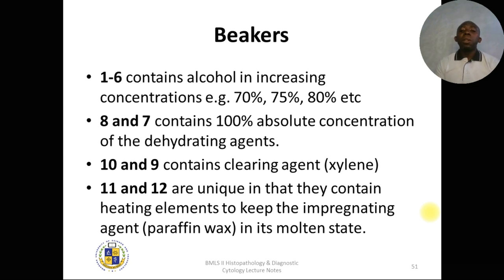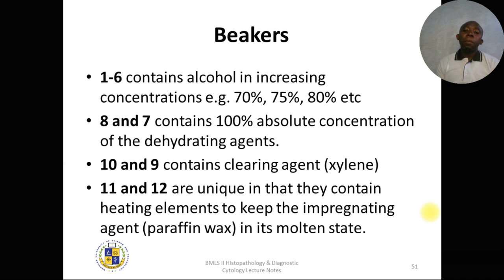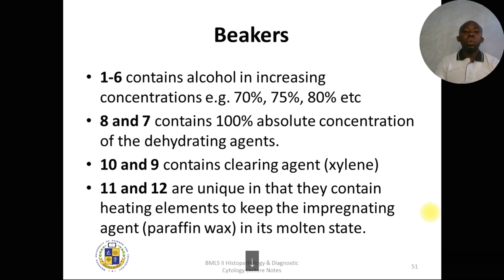Beakers 9 and 10 contain xylene for clearing — removing the dehydrant from the tissue. Beakers 11 and 12 are unique: they contain the heating element for impregnation, keeping the molten wax at a temperature above its melting point so the wax can penetrate the tissue well.